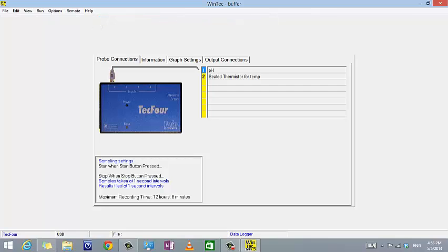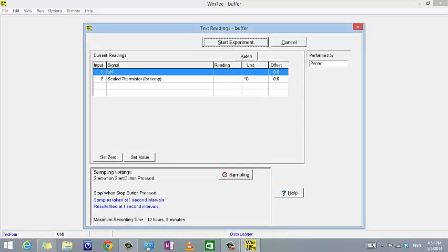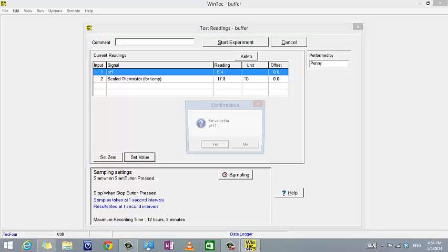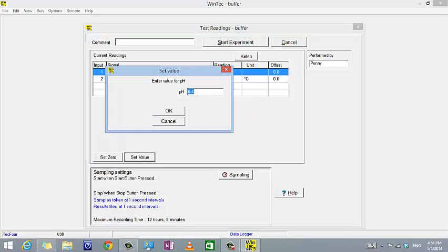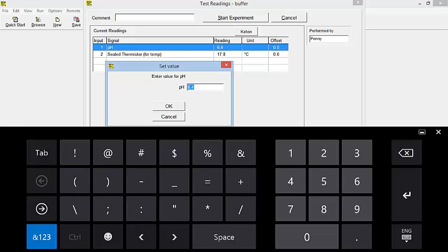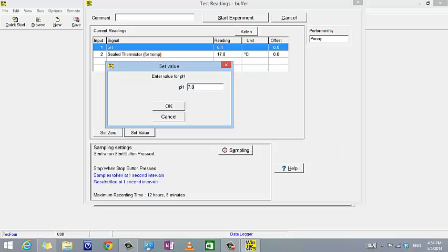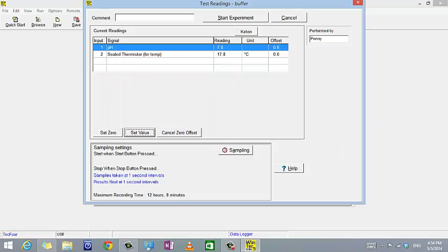Now you press run, and it will start to load up the sample. At the moment it's reading pH. This is the pH of the solution that's over there. I'm going to actually calibrate this. This is my buffer, so I'm going to calibrate this to 7. You might calibrate it to 4 if you're using a pH 4 buffer. And you look at your temperature and go, oh, 17.8. So it's about 18 degrees.